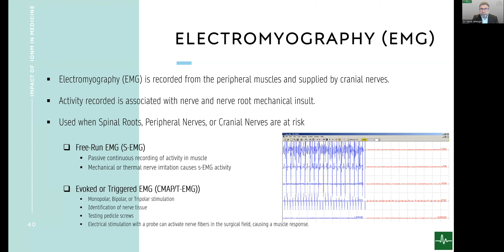So the application of EMG in spine cases is to test the pedicle screw at the cervical, thoracic, and lumbar levels. If the screw is in the pedicle and in bone, and you stimulate the screw with current, it takes much higher current to get a response because the bone has insulation. But if there's a micro breach or major breach, the threshold drops significantly, and we get these responses at a very low current. So we can identify it very quickly and with higher accuracy than the C-arm. The O-arm has a much higher accuracy than the C-arm, but triggered EMG has much higher accuracy. The literature says about 96% compared to 65% with the C-arm.